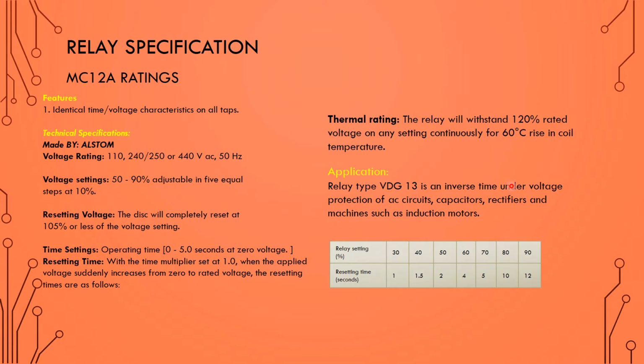Now we'll see the relay specification. The feature is an identical trip time versus voltage characteristic with all tappings, and it also has an auxiliary power supply requirement. But in the case of the over voltage relay, that requirement was not there. Then for the technical specification, the voltage rating is 110 volt, 240 volt, 250 volt or 440 volt. The relay we are going to test is 110 volt.